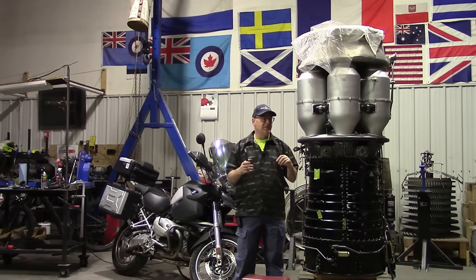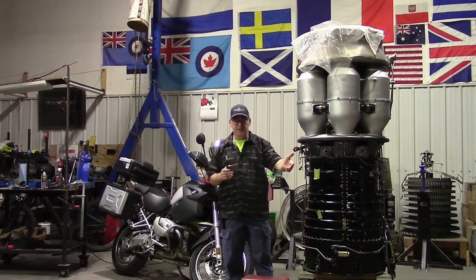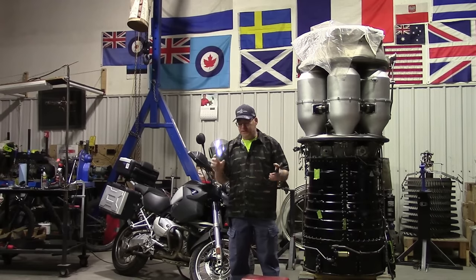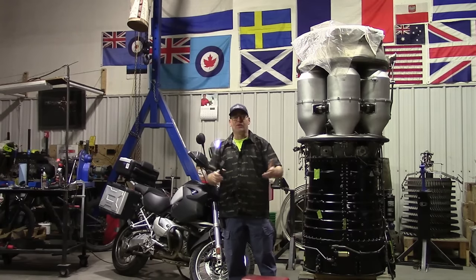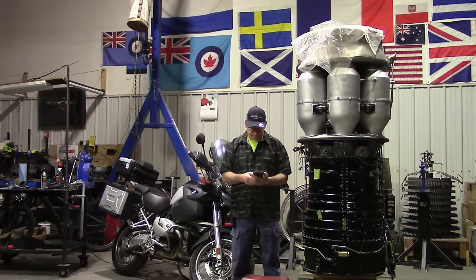If you put a different engine in, they're all different shapes, sizes, and capacities. This makes seven megawatts — I have a video called Megawatts about this. Modern engines might be more efficient, lighter, and might make 15 or 40 megawatts. The utility gets to decide, but there's no seven-megawatt drop-in replacement. You can use an eight and turn it down — less efficient — or use two 3,500s. But changing means completely designing and installing a new stand, fuel system, electrical generator, inlet, exhaust, and building — millions and millions of dollars. That's why they stay in use so long.